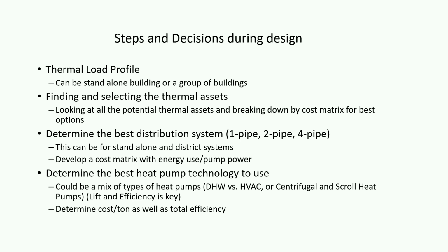So, some steps within the design process, especially early on. As I mentioned, first and foremost is that thermal load profile, really understanding the dynamics of the building. How much glass do you have? Generally you have a lot of glass in tall buildings, so again we're flipping to probably a cooling dominant application. Then of course your solar gains from morning to evening, how that changes within the building, and how much diversity you have within the building. All those things become critical to designing a geothermal system, so you can understand how to leverage that diversity, versus a traditional system where you're just turning on a boiler or a cooling tower. Maybe we're also incorporating other parts of the building systems like domestic hot water. So adding all that into your thermal load and getting a granular thermal load profile is really important.